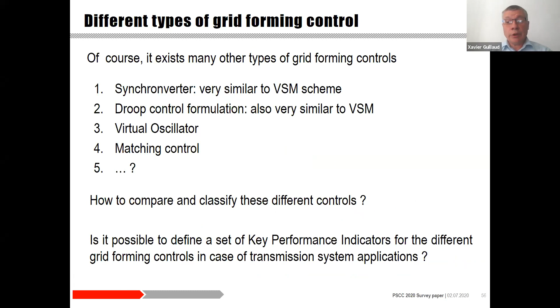First point is about the active power response time, which is extremely important. Is there an inertial effect? If so, how to characterize this inertial effect? What kind of frequency support is provided? What is the dynamic of the voltage control? What about the robustness of the control with respect to the grid impedance at the VSC? Usually the grid forming control is quite robust, but it has to be checked and studied. How is this grid forming converter protected against overcurrent, and also what about the resynchronization after a fault?